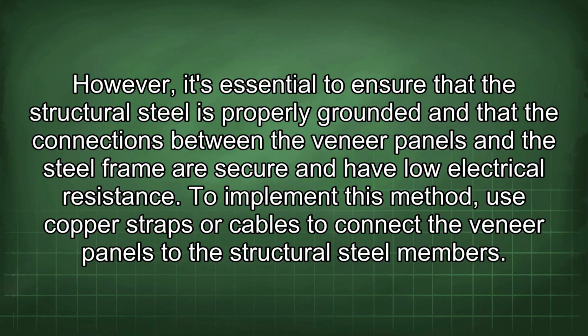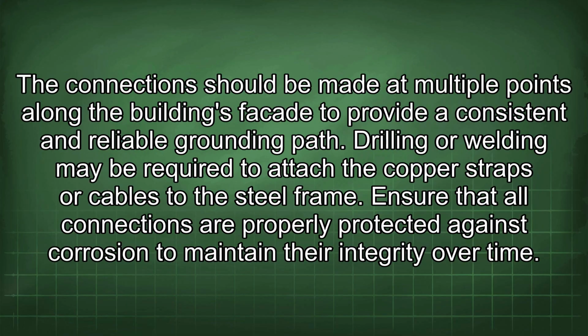To implement this method, use copper straps or cables to connect the veneer panels to the structural steel members. The connections should be made at multiple points along the building's facade to provide a consistent and reliable grounding path. Drilling or welding may be required to attach the copper straps or cables to the steel frame. Ensure that all connections are properly protected against corrosion to maintain their integrity over time.